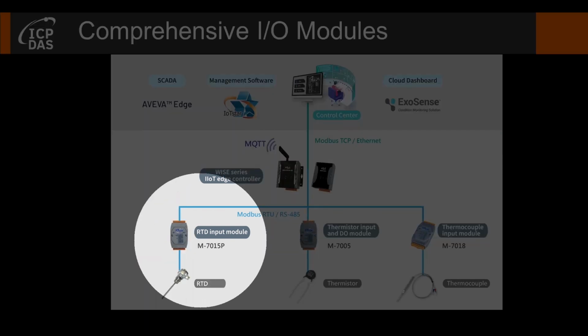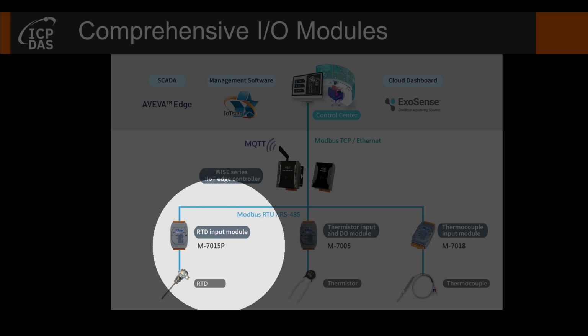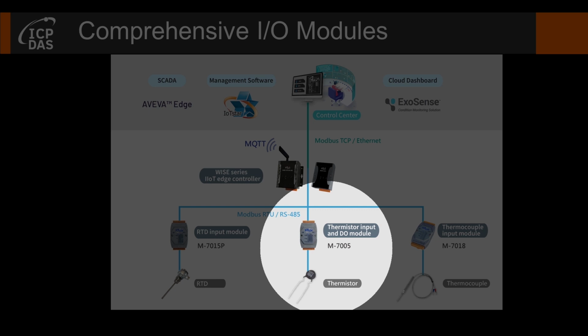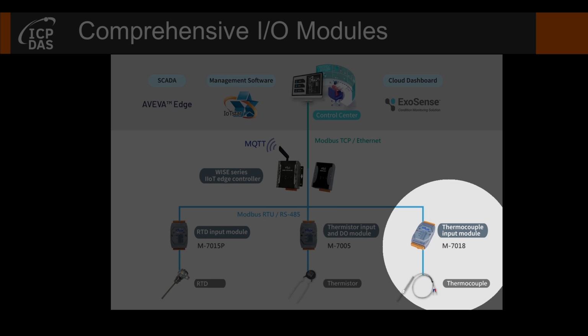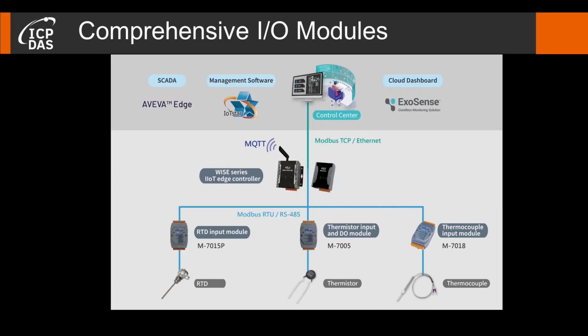For example, the M7015P RTD input module can be adapted with the RTD sensor, the M7005 thermistor input and DO module can be adapted with the thermistor sensor, and the M7018 thermocouple input module can be adapted with a thermocouple sensor. By using various I/O modules provided by ICP DAS, combined with the WISE series edge controllers, the temperature data can be easily collected and transmitted to the control center to achieve remote temperature monitoring.